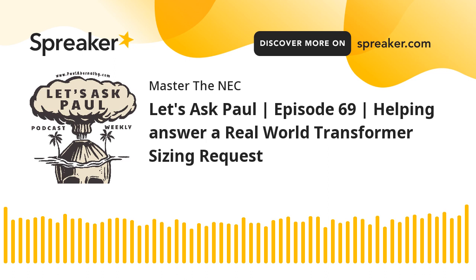Now, a couple observations first. The disconnect that's required for the transformer that you're putting at the actual transformer, you may be able to get away without. Now, I'm not trying to tell you what to do. I'm just telling you how you might save a little money depending on the condition you might be dealing with. So if you're dealing with that transformer, you may be able to use the breaker that's back in the actual 480 volt panel as your disconnecting means, as well as the overcurrent protection for the primary side of the transformer. It might be able to serve double duty as the disconnect, because you can go over and look at 450.14.